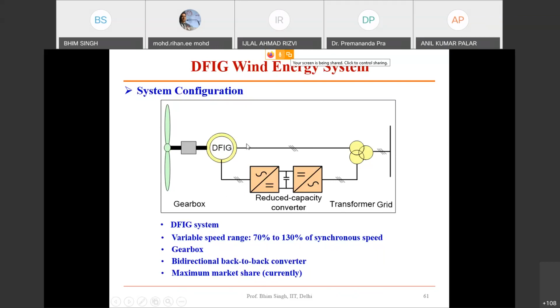The efficiency of this machine is high because you are exceeding neither the voltage nor the current of the stator and rotor. Mind it. So neither the core losses nor the winding losses are increased. So losses correspond to 1 megawatt, while power generation is 1.5 megawatt. The machine is quite safe because losses are not going beyond rated, and it generates around 50% more power. So it supersedes the efficiency of a conventional synchronous generator also. That is the reason this DFIG is really preferred in this application.